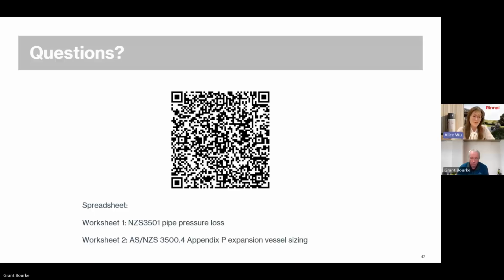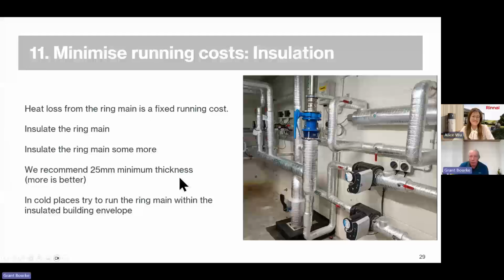And the final question is actually from me. Who installed the insulation in that plant room? Right, so Grant's favourite picture. The commercial plumbers did that job. They contracted out that insulation to some refrigeration guys that normally work with heat pumps. Obviously, if you don't properly and fully insulate a chilled water line, condensation will drip off it onto ceiling tiles and things and damage the building. So they are very, very pedantic about how they go about it, because they're used to doing chilled water lines. So sadly, that one wasn't a plumber.